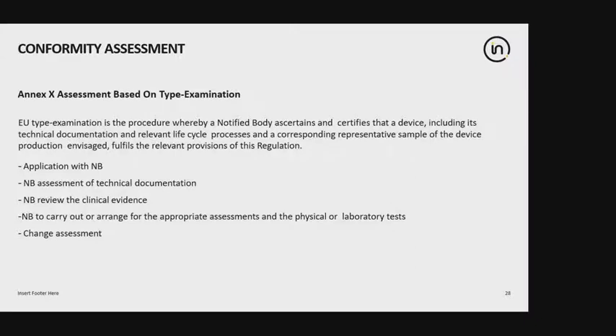The next conformity assessment system is based on type examination. You can consider the EU type examination as a design examination of the product, which is necessarily carried out by a notified body. They check the overall technical documentation, they review the clinical evidence which you have provided, they perform physical tests on the device, and then issue a certificate. Any change to the device needs to be notified to the notified body. They will evaluate whether the change is significant or not, and if the change is significant, then a re-audit or a reassessment needs to be performed.